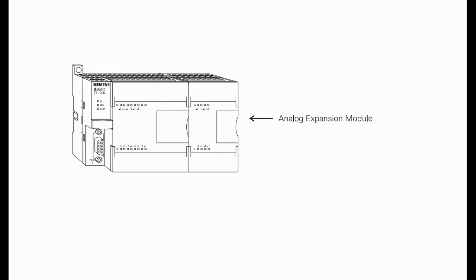A PLC cannot process these signals in an analog form. The PLC must convert the analog signal into a digital representation. An expansion module capable of converting the analog signal must be used. The S7-200 analog modules convert standard voltage and current analog values into a 12-bit digital representation.